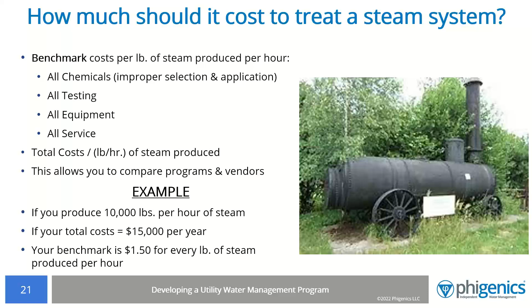To calculate them, add up the cost for all chemicals, testing, equipment, and service, divided by the number of pounds of steam your boiler produces per hour. So for a 10,000 pound per hour boiler and a total cost of $15,000, your benchmark cost is $1.50 per pound per hour. There are sometimes reasons it can be well above or below, but you want to understand what they are and if those reasons are justified.